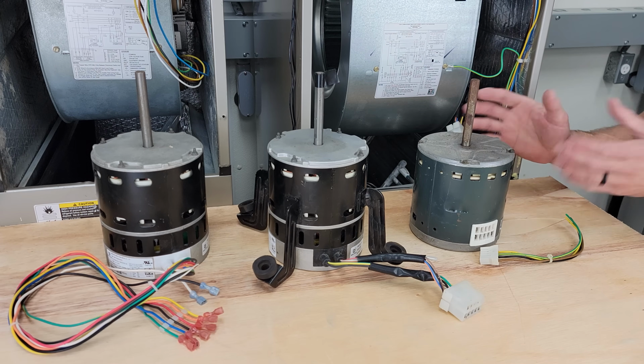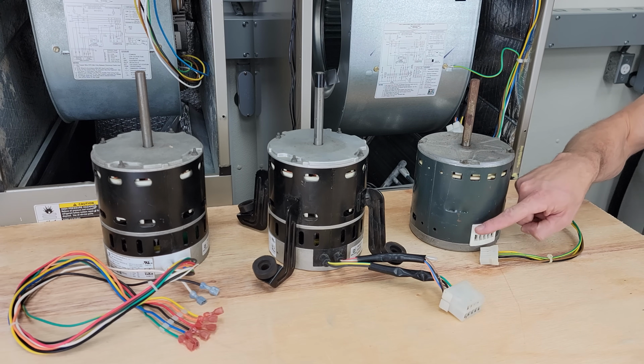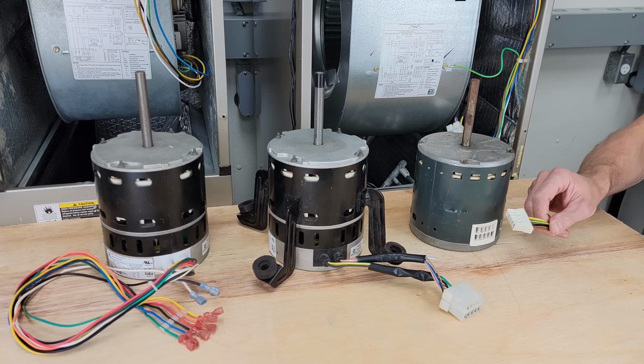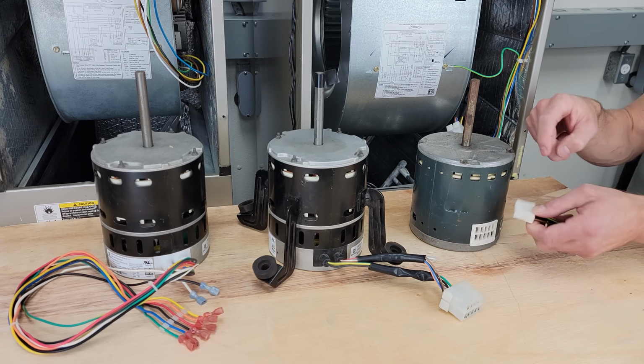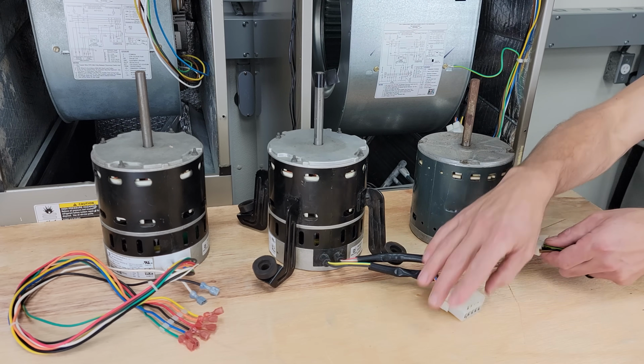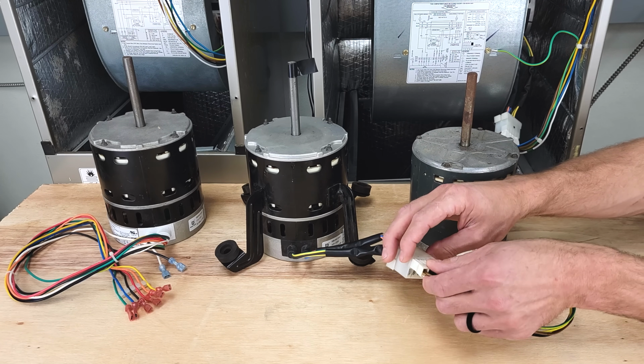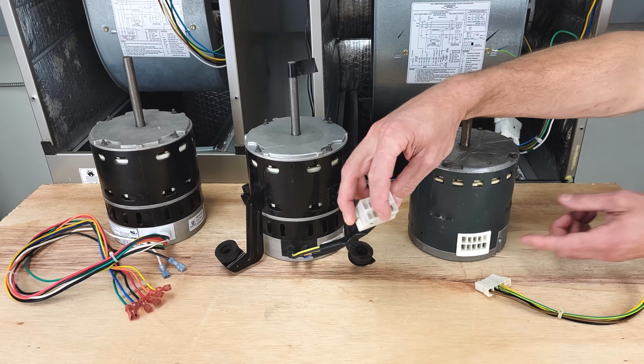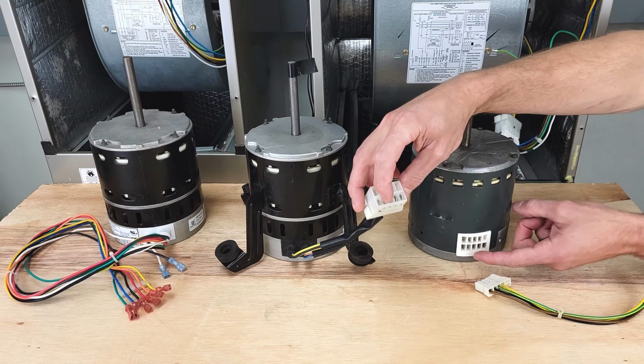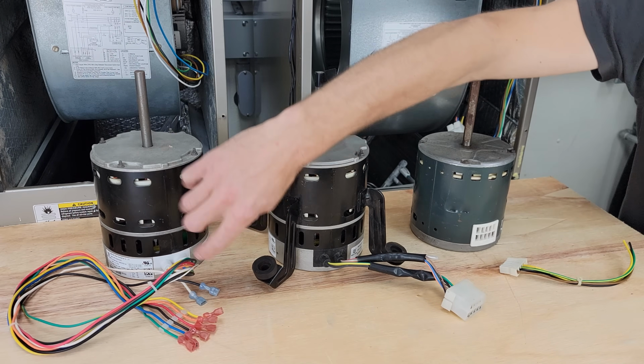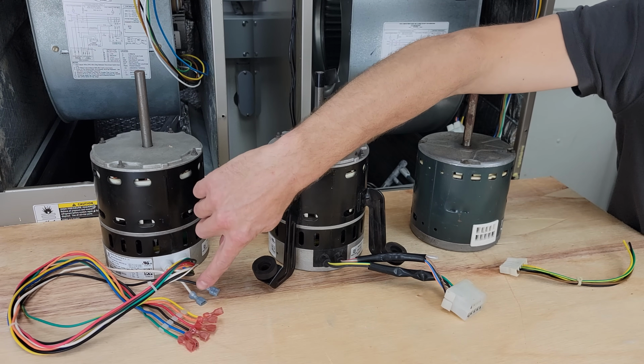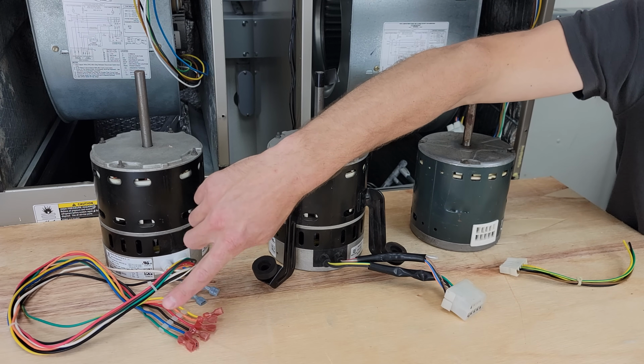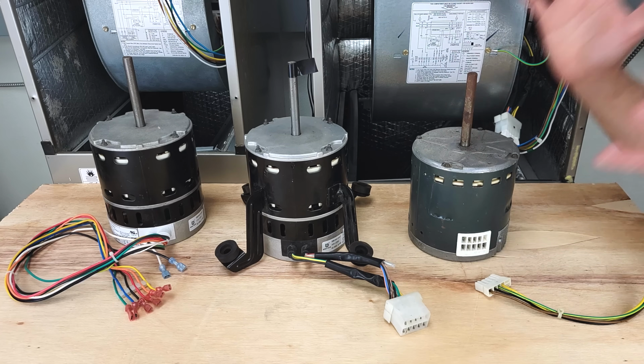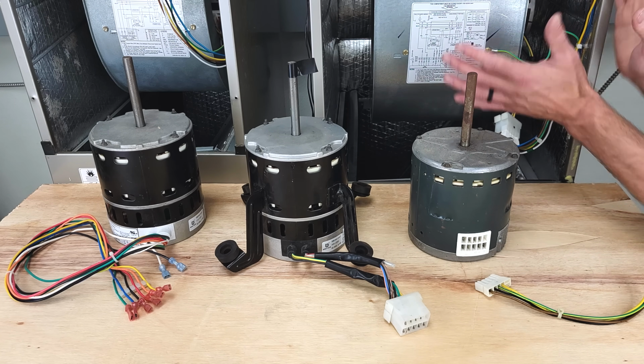The other thing to note is that you're going to have two sets of wiring. One set's going to be for your power wiring, such as this right here. And you can notice this little blank spot, so you can plug that in right there. Here you have your power wiring right here, and in the lower section you're going to have your 24 volt speeds. And so over here you have a 120 volt version with your power wiring common, and then your 24 volt speeds along with your common. And so now I want to take it in and troubleshoot on an actual system.